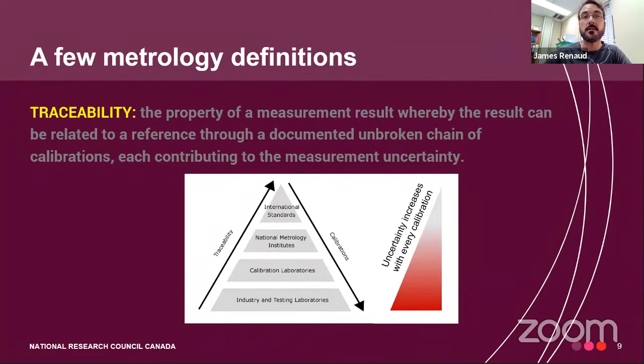have the traceability. One characteristic is that with every layer of calibration, every link in the chain, you add uncertainty to your measurement. The chain of traceability allows any measurement to be referenced to higher levels of measurement back to the original definition of the unit. It really is an important part of the measurement. One of the best ways to understand an instrument's measurement performance is to assess its accuracy. The instrument should be calibrated against an SI traceable reference to ensure the quality of the measurement data. Quality data in turn provides reliable information for decision making.